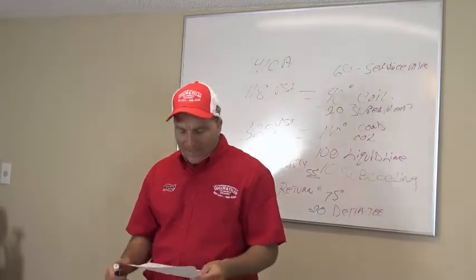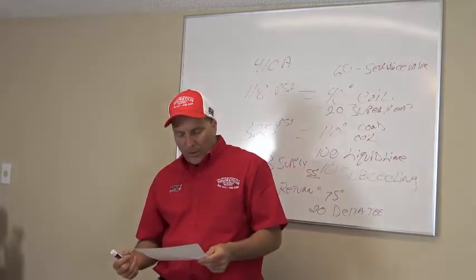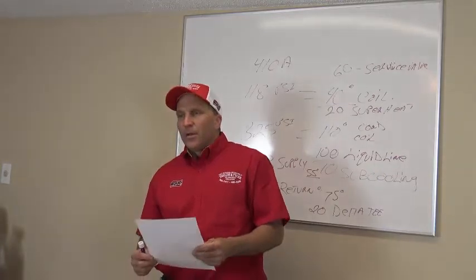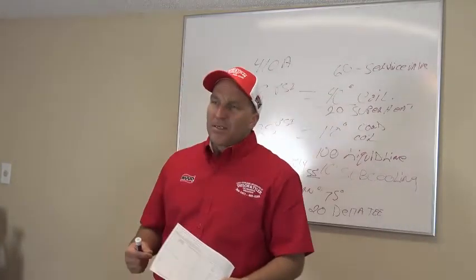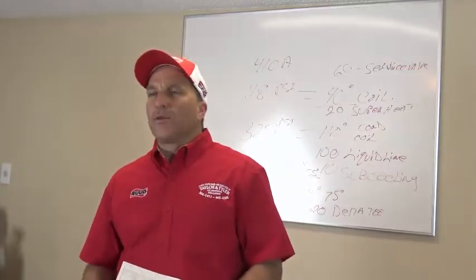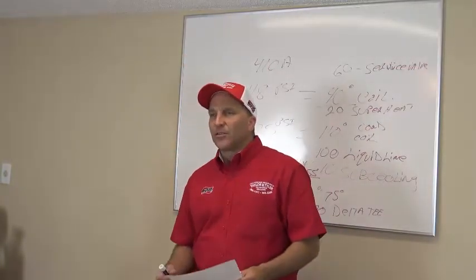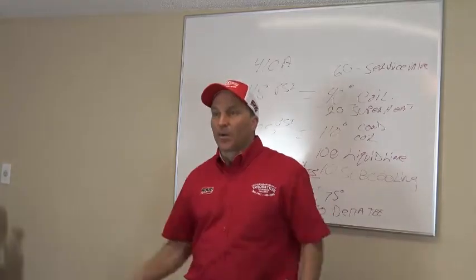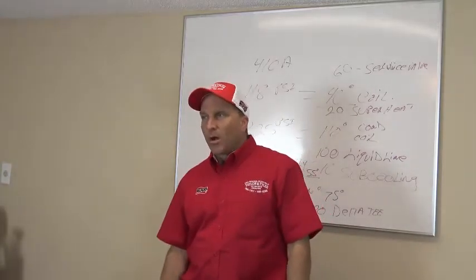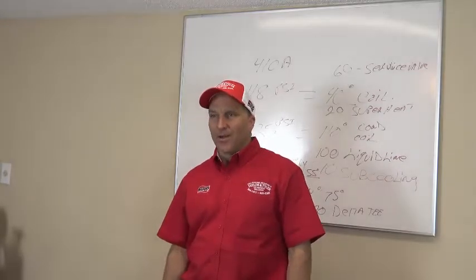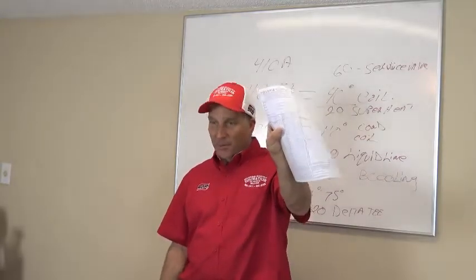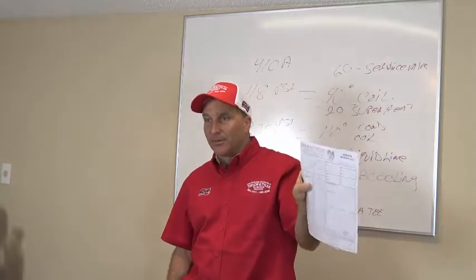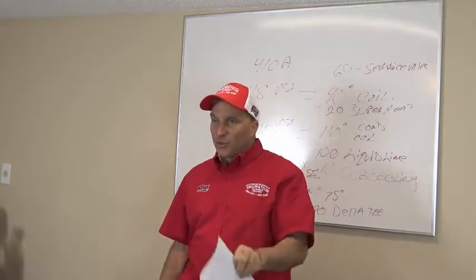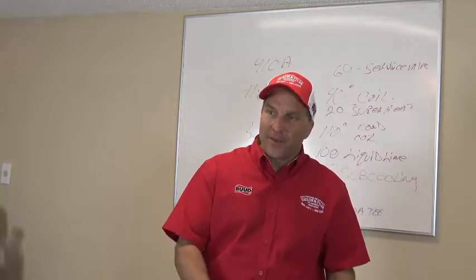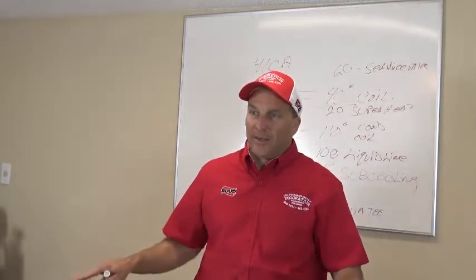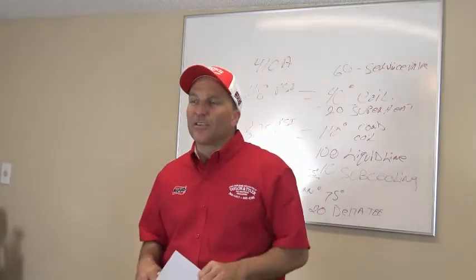I want to know if the condenser coils are okay, or are they dirty, or are they filthy. Well, if you walk up to a condenser coil, listen to what I'm telling you, guys. If you walk up to a condenser coil and it's got dirt packed all the way around it, it's filthy. If you walk up to it and it just doesn't look dirty, you know what? You've got to check off dirty, because it probably hasn't been cleaned in the last year or two. Unless you know that it was cleaned last week or last month, it's dirty. End of story.